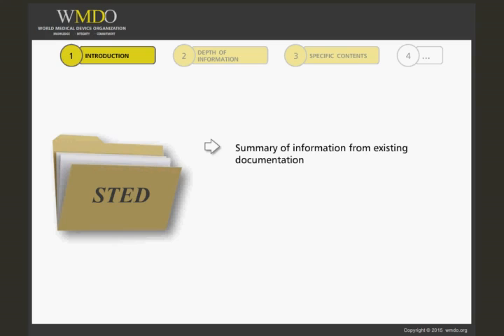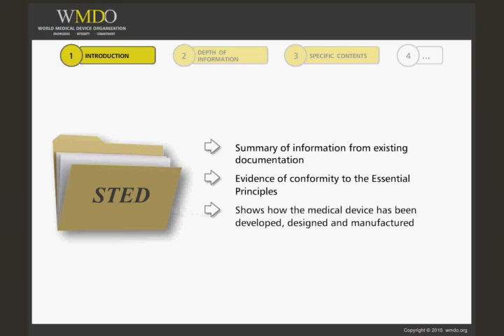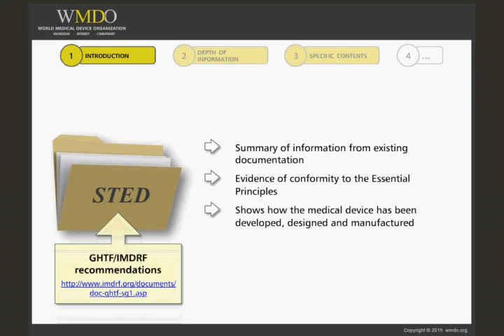provides evidence that the medical device conforms to the Essential Principles for quality, safety, and performance, shows how the medical device has been developed, designed, and manufactured. The GHTF, now replaced by the IMDRF, has provided recommendations for the STED that you can find on the IMDRF website.